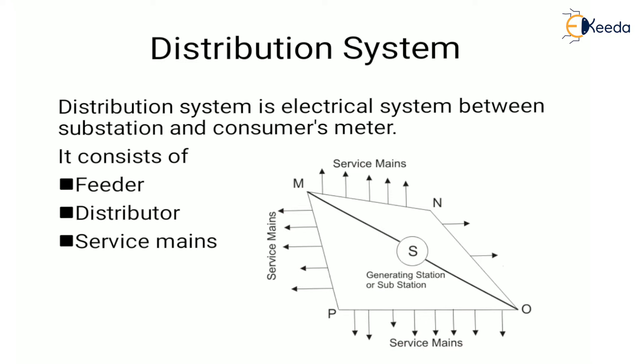The current through a distributor is not constant because of the tappings. Voltage along its length is the main consideration for the distributor, since the limit of voltage variation is plus or minus 5% of the rated value. Here MNO and MPO are distributors.